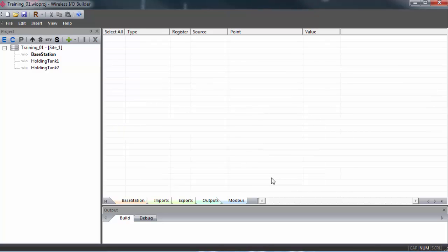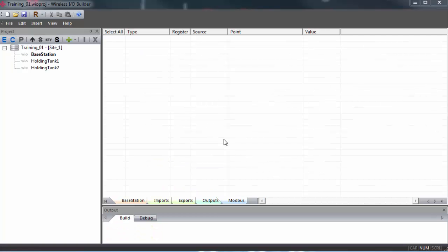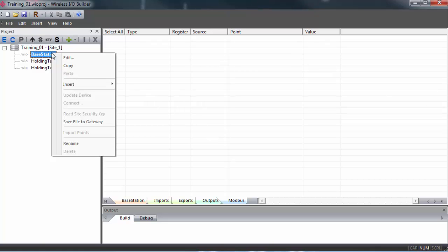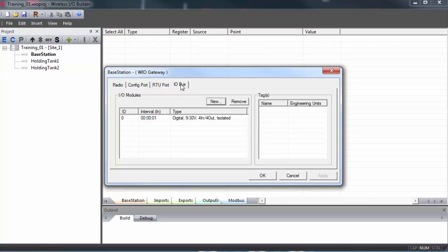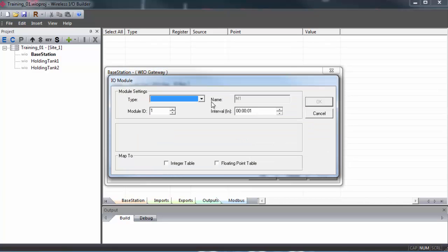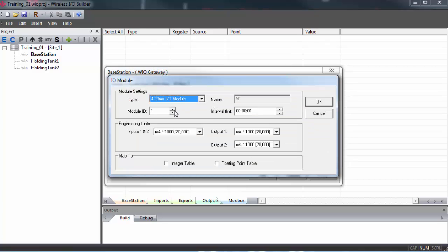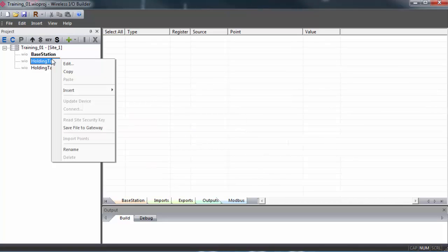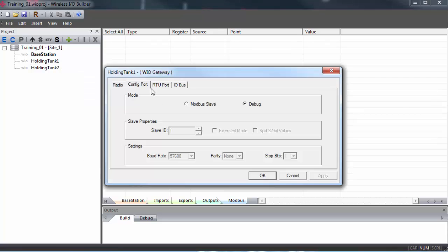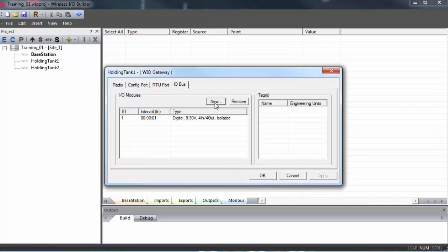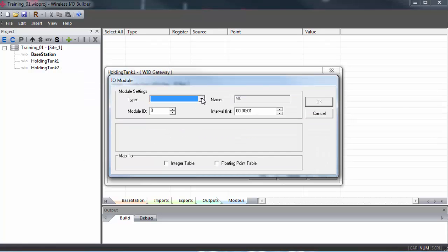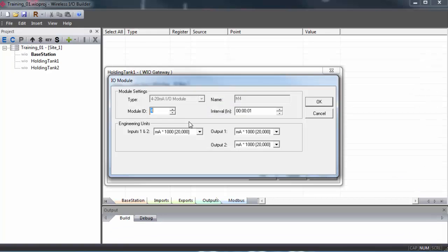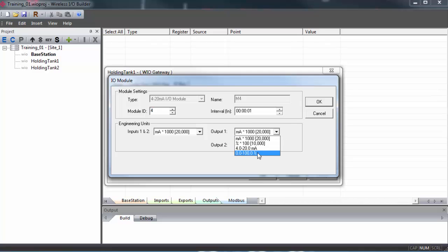And when you're finished, click OK. And then click OK again on the gateway properties window. And we'll add a digital IO module for each of the other gateways, making sure each one is configured with the proper module ID. Now for clarity, I'm giving each new module that I add to the project its own unique ID. But really, you only need to worry about the modules connected to each individual gateway having unique IDs amongst themselves. So now that we have some discrete IO added to each of our groups, I'm going to go back in and add an analog IO module to my base station. This will be a 4 to 20 milliamp module. And we'll make sure the module ID is right. And we can select what engineering units we'd like to use. I'm not going to make any changes here. So click OK and OK again. And now I'll add the same module to one of the other groups.